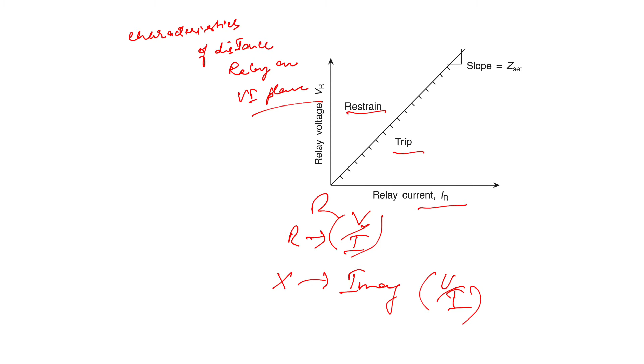Then we have the internal fault and the external fault, and it is represented by the faulty transmission line, that is R and X. However, when we map the V and I axis, it is represented by this circle. Inside the circle is the trip region, and this is the restraint region, and it is actually the R and X axis, where R in this case is the real part of V by I, and X in this case is the imaginary part of V divided by I.